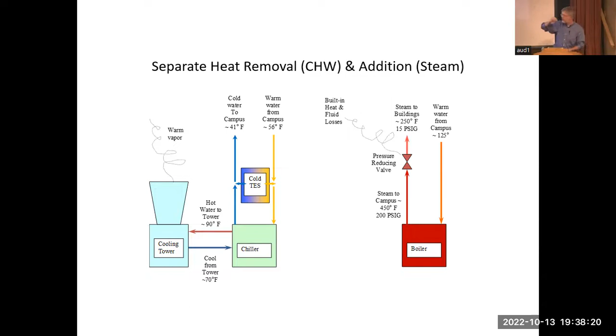We need to change this just a little bit. We're going to keep the diagram similar, but move the chiller over and call it a heat pump. That same chiller will continue pulling heat out of the chilled water system, removing heat from all the lasers, electron microscopes, and other equipment, and deliver it to the hot water system.